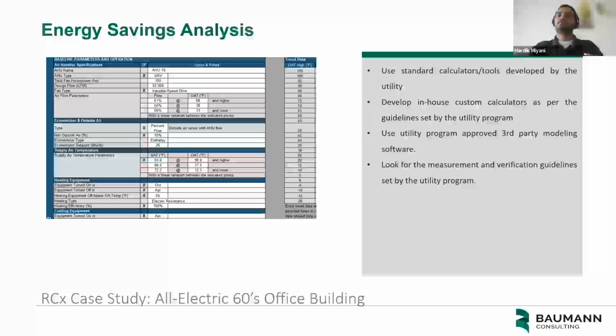Next slide. Once we identified the ECMs and reached out to the customers, we start with the engineering savings calculations. Depending upon the utility, there can be a few standard calculators already developed by utilities that we need to use, but you can also develop your own custom calculators as per the guidelines set by the utility program. There are also a few approved third-party modeling software that can be used as part of the calculation methodology, but it needs to be confirmed by the utility whether it would be okay to go ahead with energy modeling software as part of the retro-commissioning process.